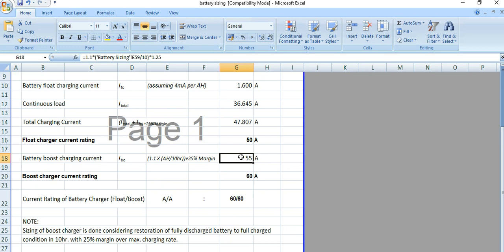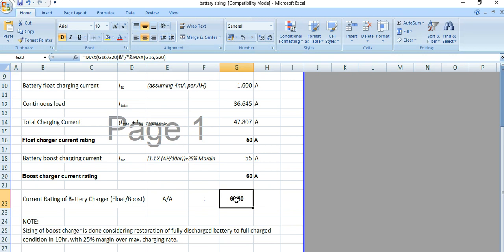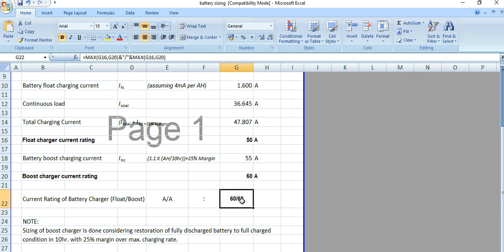So we have considered the boost charger current rating as 60 ampere. The current rating of the battery charger, both float and boost, is 60 ampere. Instead of 50, we have considered 60 ampere for both float and boost charging.